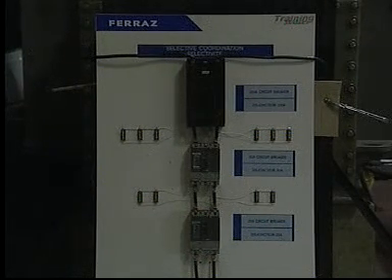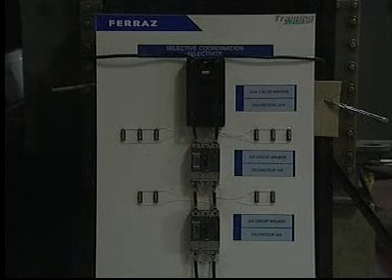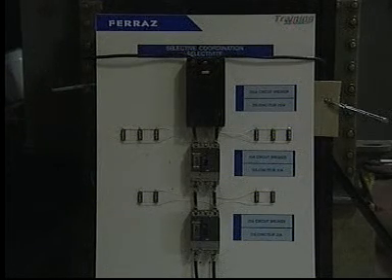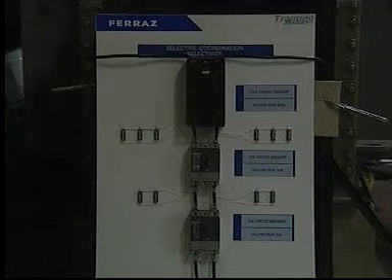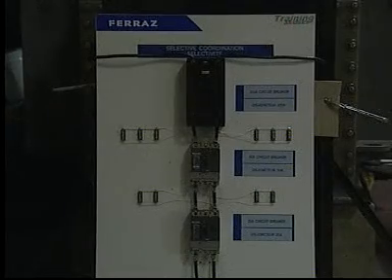The result is that all three breakers open, causing a total system blackout. This could be predicted, since the fault current of 15,000 amperes is well above the 2,000 ampere instantaneous trip of the main 200 ampere breaker.